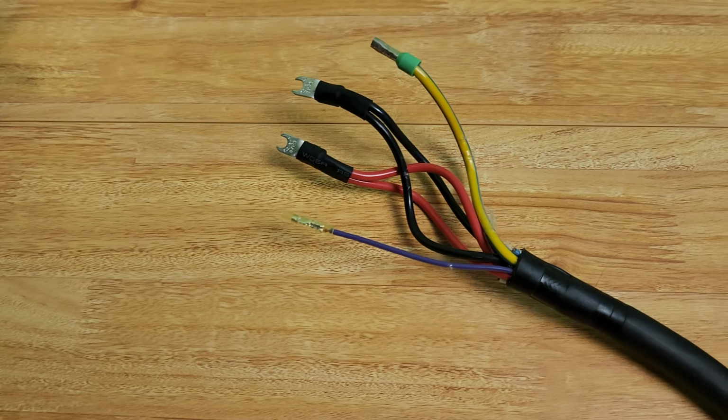So we're going to go ahead and turn this selection to number 4 manually. That current selector is now aiming right at the 4, which my brain tells me should be 40 amps. Alright, so we got it all put back together now with one used, repurposed Tesla NEMA 14-50 plug attached. You can see the difference in the size here between the commercial cabling and the Tesla residential cabling. Now remember, I did back off the power physically inside, so now this is effectively only a 40 amp station, so I have nothing to worry about.